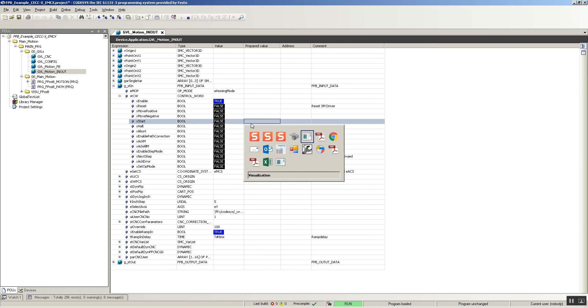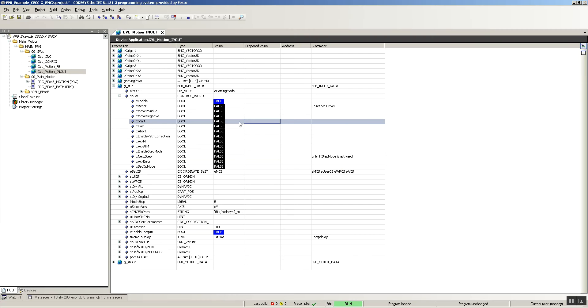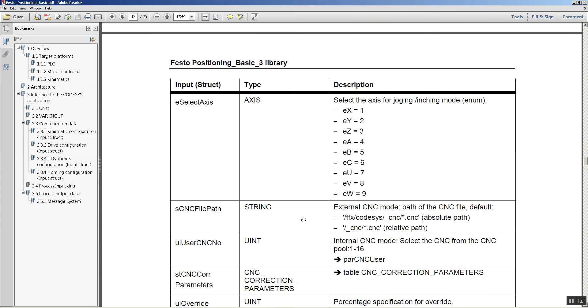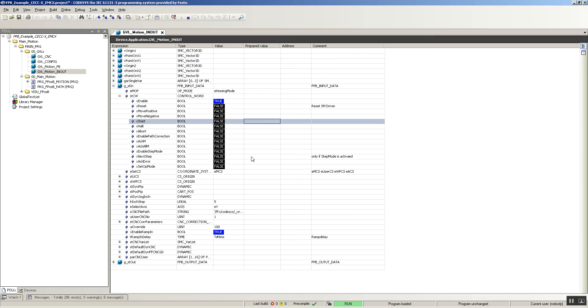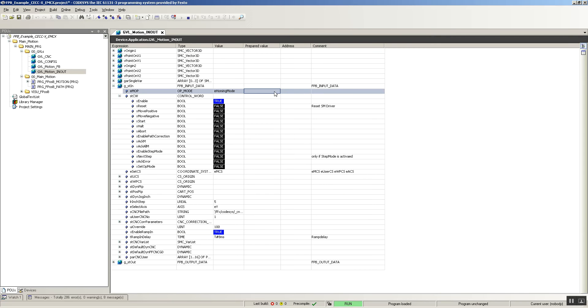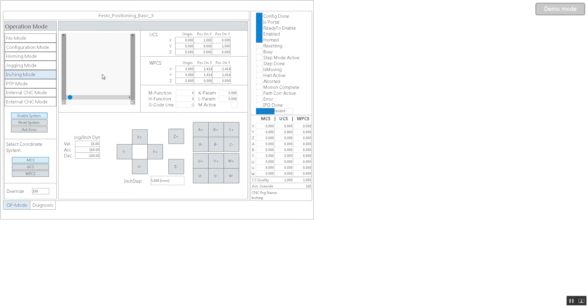Now let's look at jogging inching mode — that's technically the same as jogging but let's try it. Inching is mode 40. So I write 40, write that, and then set the operation mode. I'm on inching now. Right now the inch step is five millimeters, so each time I set move positive or negative, it's going to do it in five millimeter increments.